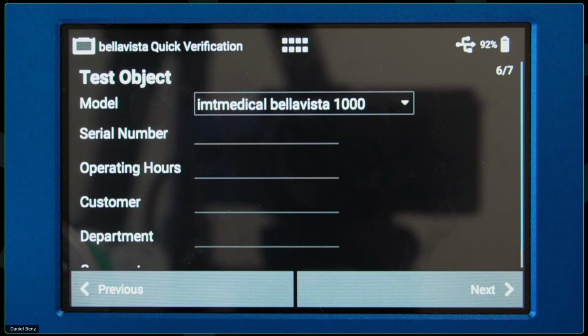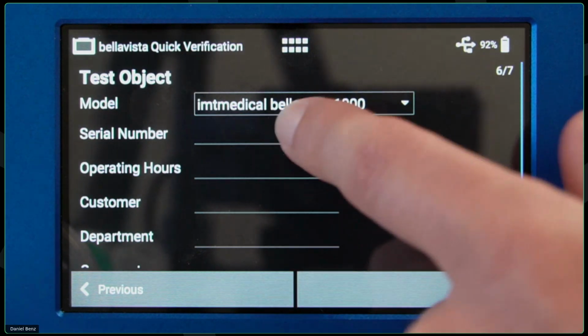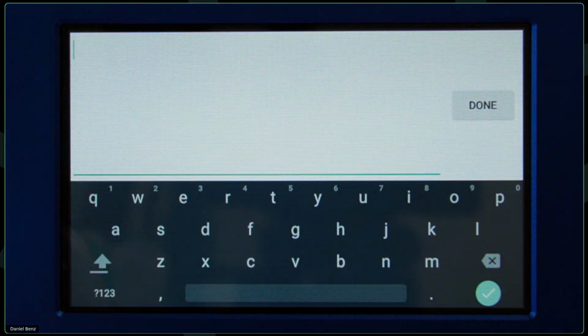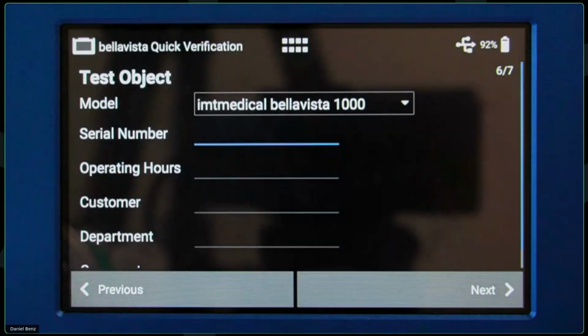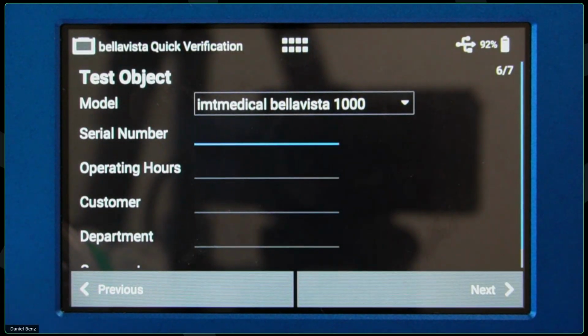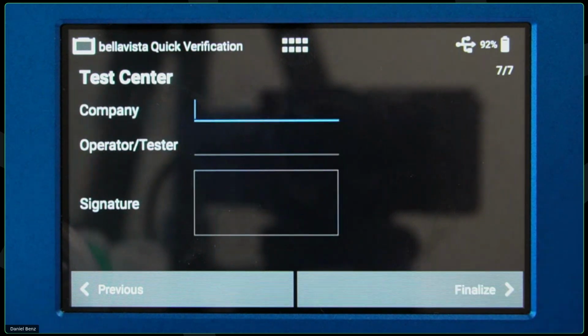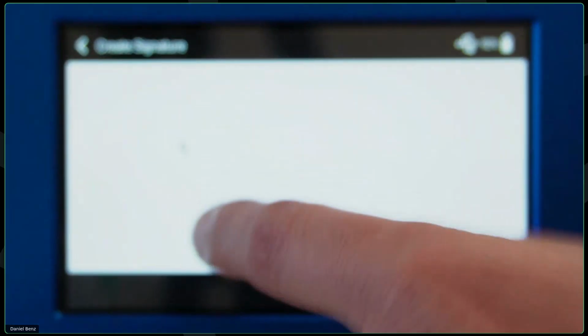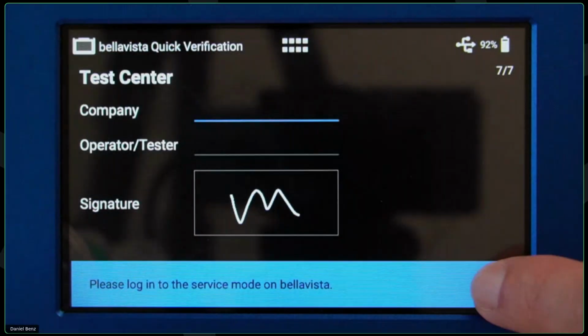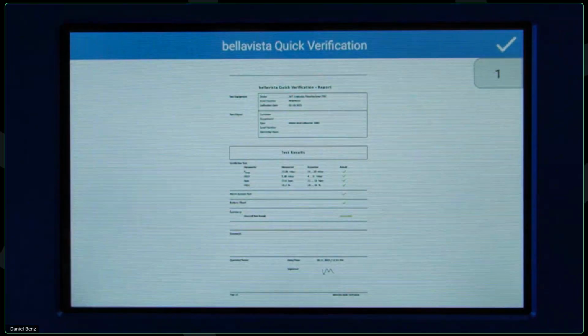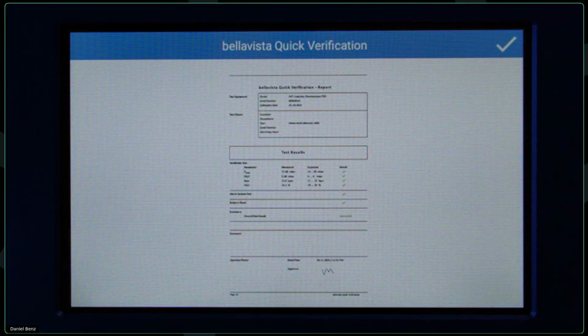At the end of each application, usually also the manufacturer wants you to document some things. So here, for example, serial number, operating hours, etc. So we can just type here, there's a keyboard showing up. We can, for example, enter the serial number of our device under test. And then at the very end of each application, you can always add information about yourself and even add your signature here. And then all that is finalized in a report. So you have objective proof that you have tested it exactly as per the manufacturer specification.